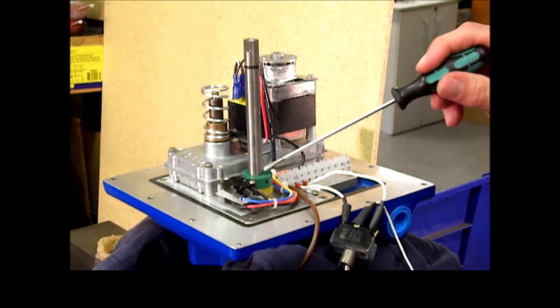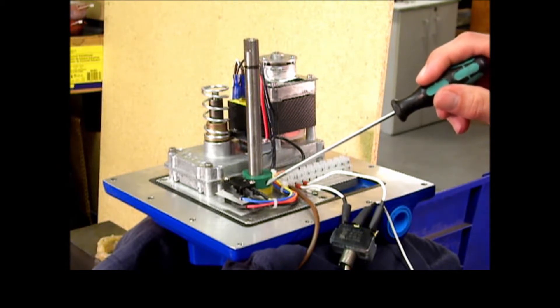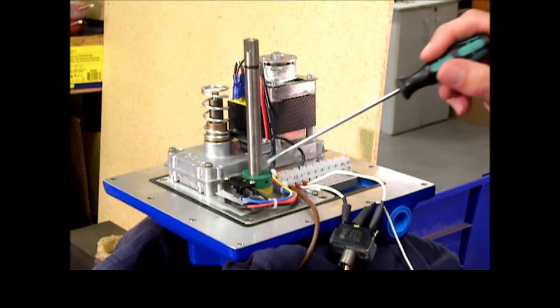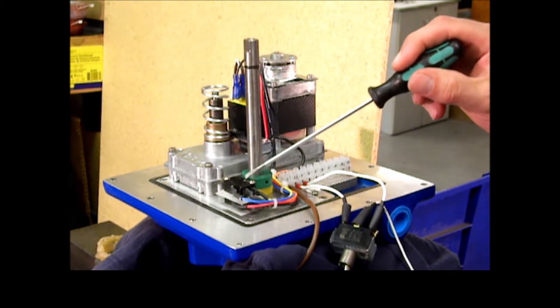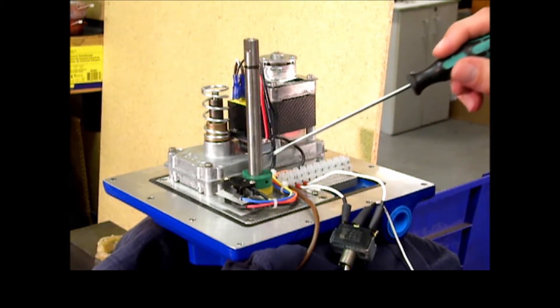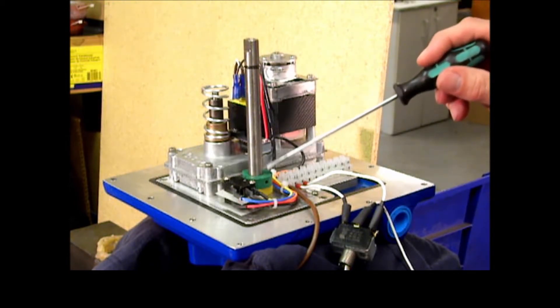And again, if the positioning is not exactly right, the set screw on that cam can be loosened and the cam rotated to adjust for the trip of the switch to allow either a little bit more or less on the open.